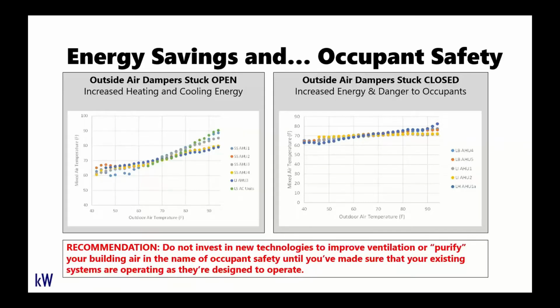And there certainly is a time and place and necessity for those in some cases, but my strong recommendation would be to make sure that you have evaluated your existing systems first. Make sure you don't have these types of issues that represent low-hanging fruit to significantly improve your occupant safety through ventilation and temperature control, and at the same time will actually yield energy and cost savings to you as opposed to significant additional capital cost and operational cost by adding these additional air purification and filtration systems.